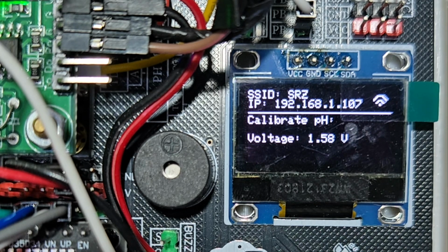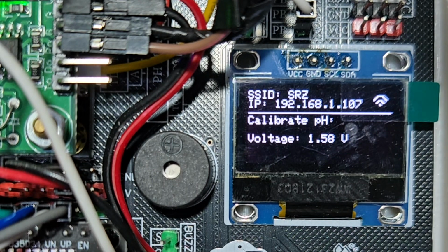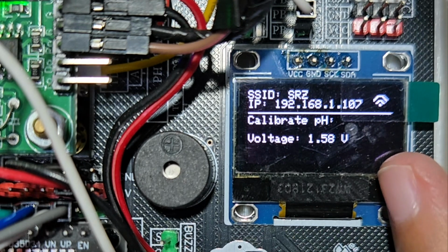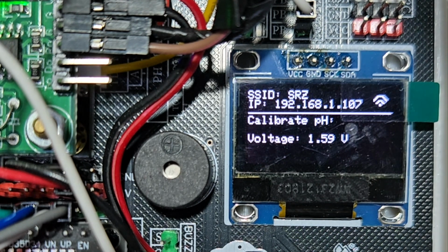And what happened is, as you can see there, there's a voltage reading on that probe. Once this water is mixed with the buffer, we simply insert the pH probe into the bottle, and then it will change the voltages based on whatever pH this is. So for example, if we put a pH buffer of 4, we note down the voltages there. Maybe it's 1.1 something. If it's 7, it should be around 1.6. If it's pH 9, it should be around 1.8, 1.9. Once the user notes that down, we go back twice.